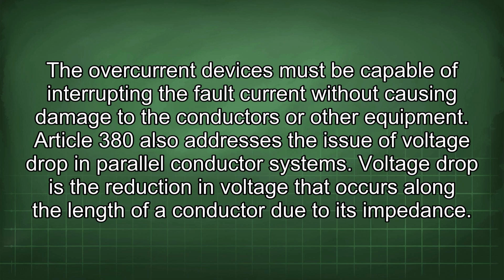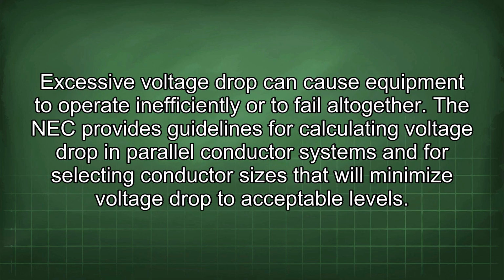Article 380 also addresses the issue of voltage drop in parallel conductor systems. Voltage drop is the reduction in voltage that occurs along the length of a conductor due to its impedance. Excessive voltage drop can cause equipment to operate inefficiently or to fail altogether. The NEC provides guidelines for calculating voltage drop in parallel conductor systems and for selecting conductor sizes that will minimize voltage drop to acceptable levels.